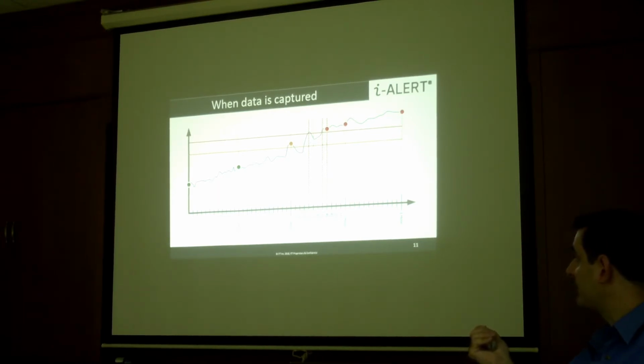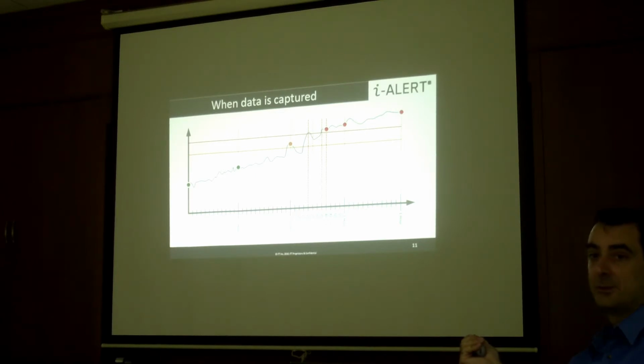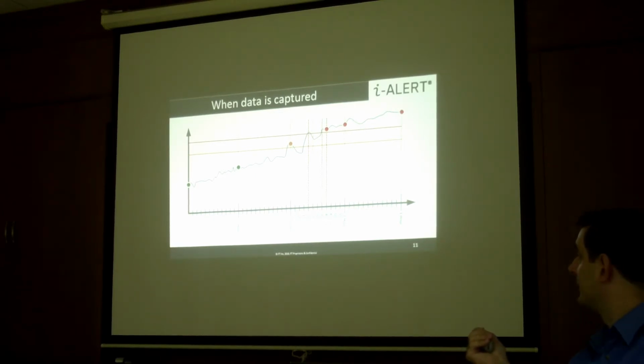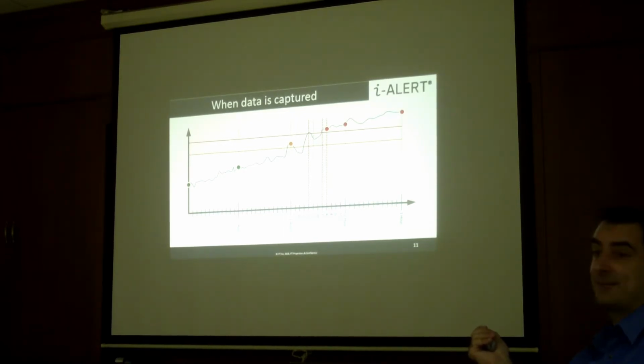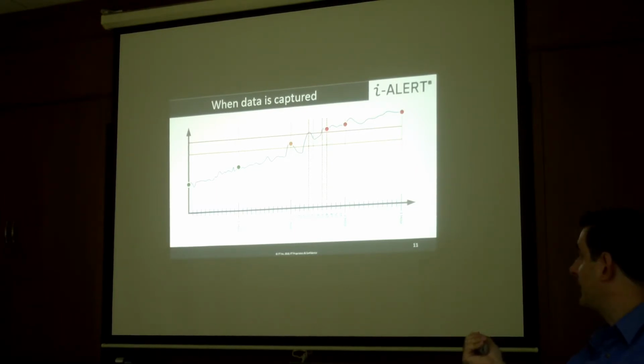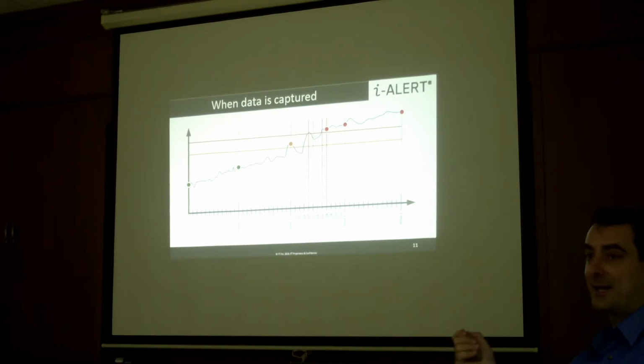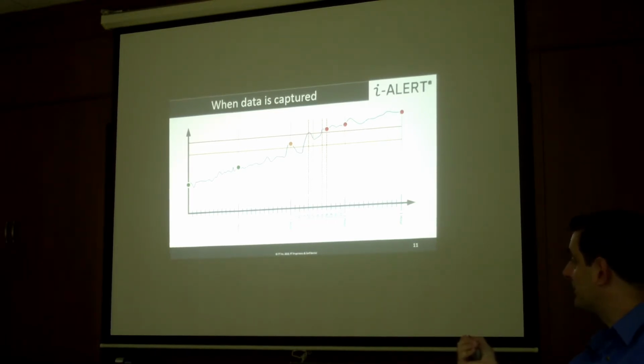Here, this vibration goes up and it crossed the alarm. But within 5 minutes, it went down. So 20 minutes, it was up. 5 minutes later, it was below. So we don't save a data point. But here, it went above the alarm at 35 and then 40 minutes. So then we save a data point. This is different to the 1 hour data point. And again, when we hit the 1 hour time, we save the data point, data point, data point every hour after that. We do capture this extra data point.